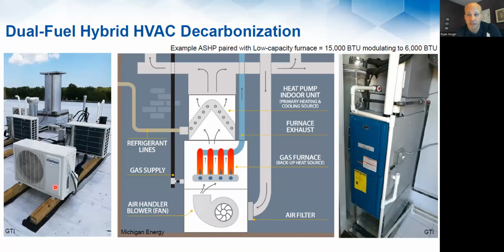I literally just throw my AC away and put a heat pump there, and then I change my thermostat wiring to accommodate this. Not every thermostat can do this, by the way. You will need a thermostat that is dual fuel capable. All dual fuel capable thermostats have an outdoor air temperature sensing mechanism. It's either a hardwired sensor that installs on the building and wires back to the stat, or some manufacturers, like Ecobee for example, get the outdoor air temperature off an internet broadcast. But the stat has to have outdoor air temperature access, and the stat has to be specifically labeled as dual fuel. I don't know why I'm putting that in quotes. It's a real thing. It has to be labeled as dual fuel, and then it'll be able to handle this.